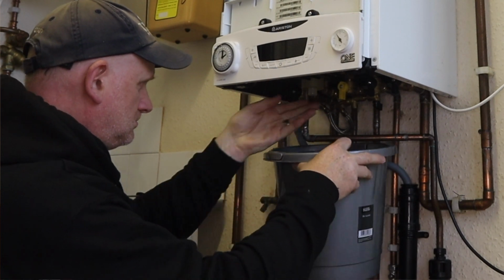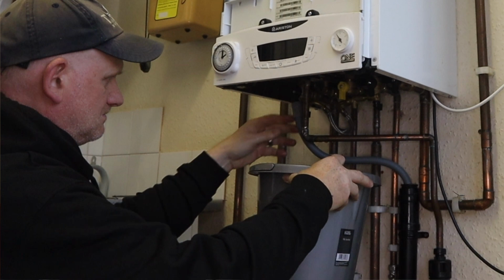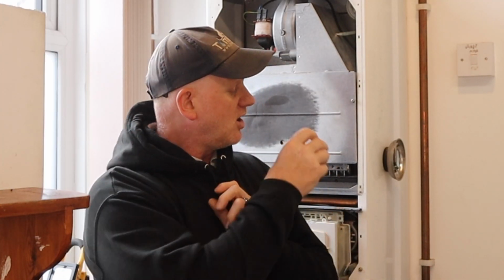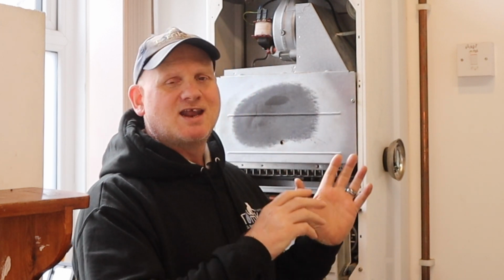Actually taking the cover off, having a look inside, cleaning any filters, cleaning the condensate trap out if you've got a condensing boiler, and checking for any leaks or wear and tear on the inside of the boiler is key when you're having a service. If the engineer is not taking the cover off, then you're wasting your money. Basically, I would say if you're paying less than £100 for a service, that's not what you want. You want a top quality service done where the engineer comes in, spends the time stripping the boiler, cleaning the boiler. Not every boiler needs stripping and cleaning every year though. Some of them are on a 4 or 5 year cycle, but actually going in and checking it and making sure it is going to last through the winter is a key part of servicing.